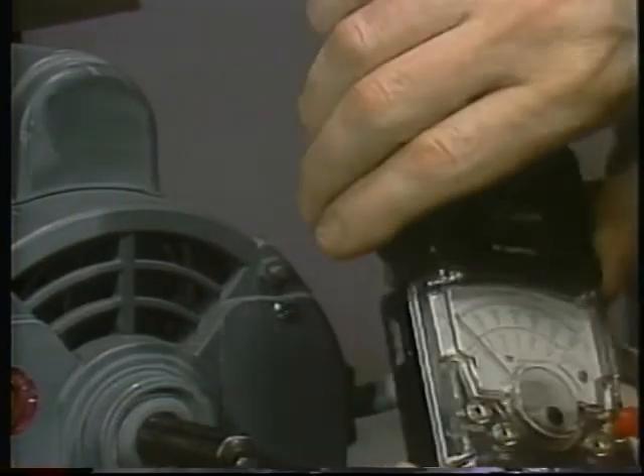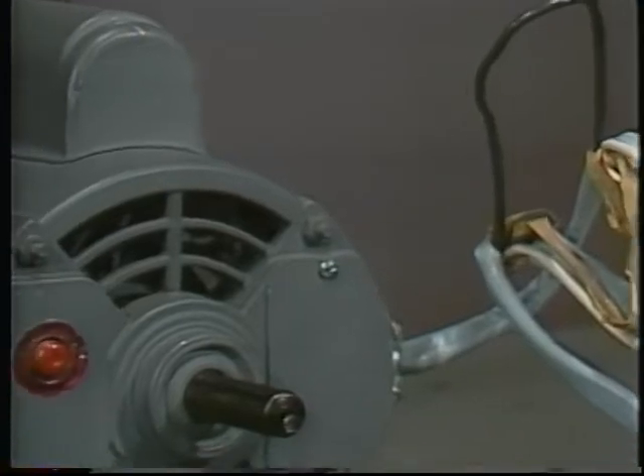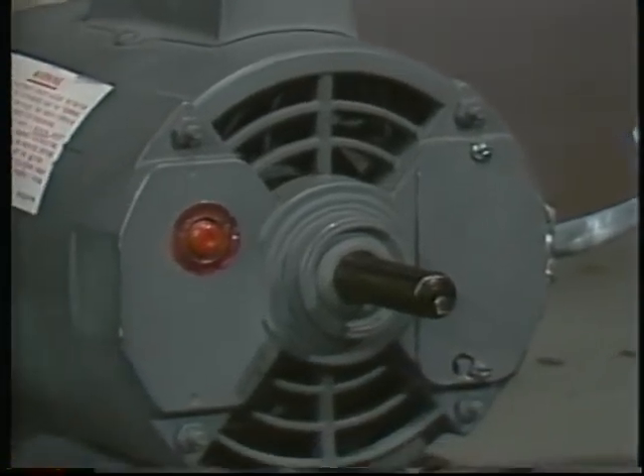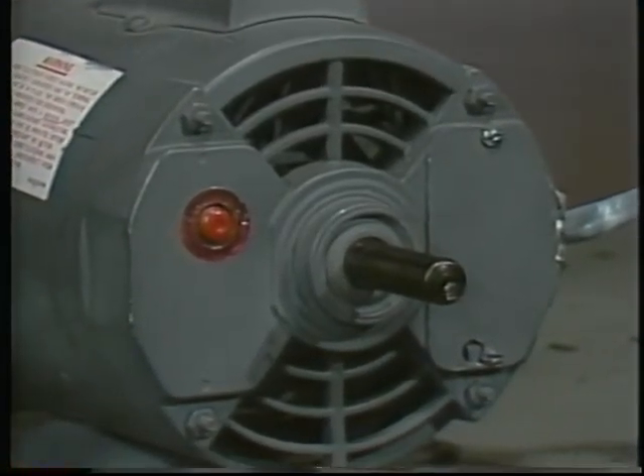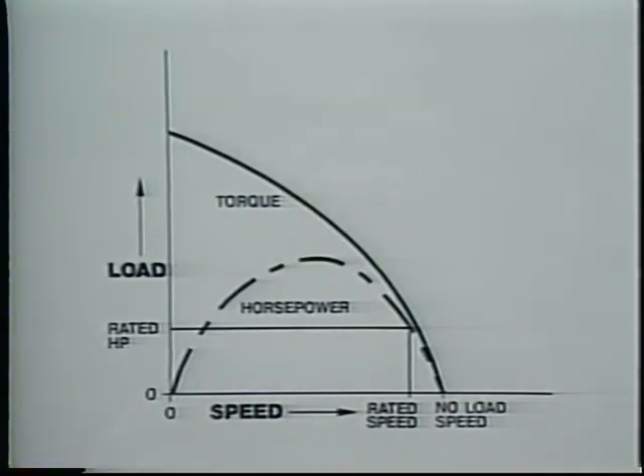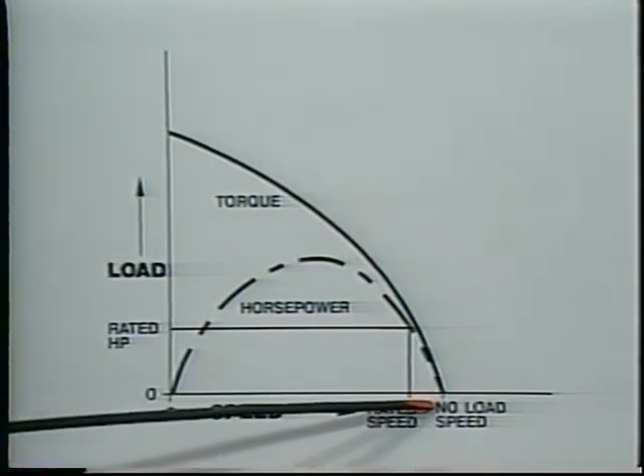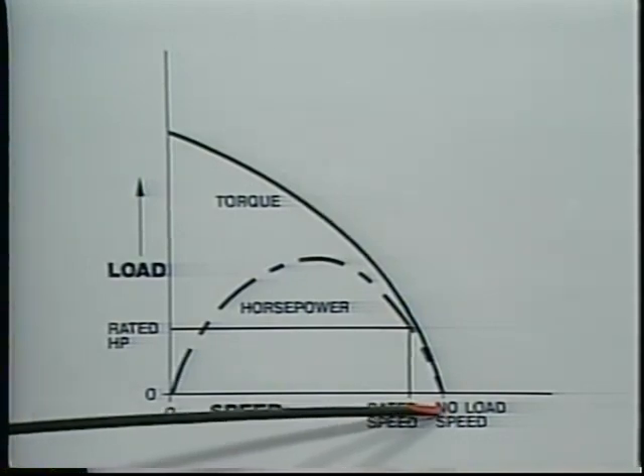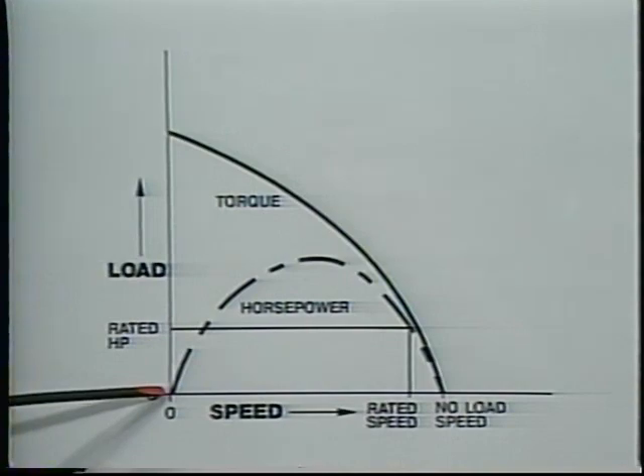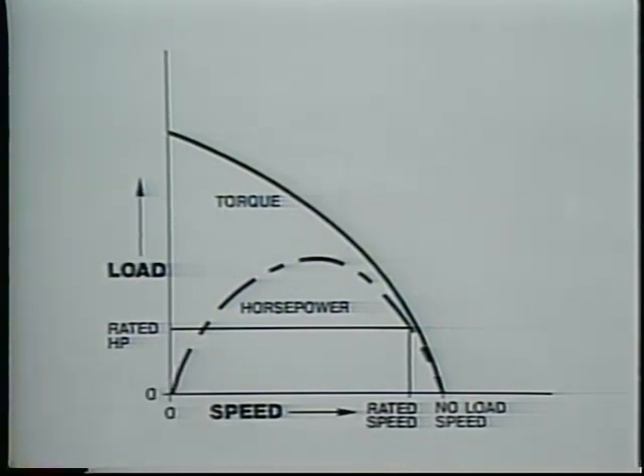We can learn more about motor life and efficiency by taking a closer look at how speed and torque affect horsepower. If we plot motor horsepower output along with torque, both are zero at no load — zero torque means zero horsepower. At stall, horsepower is also zero: nothing is moving and no work is being done, even though the motor is drawing a lot of current.